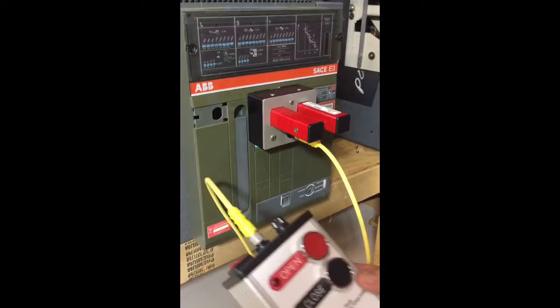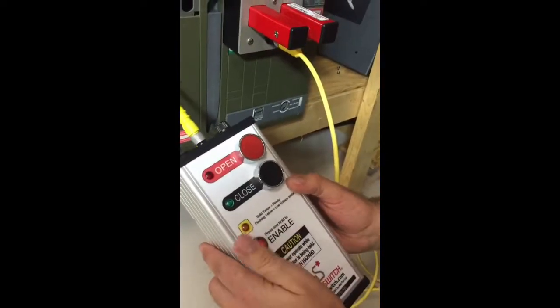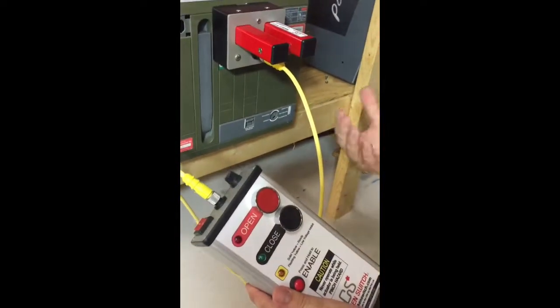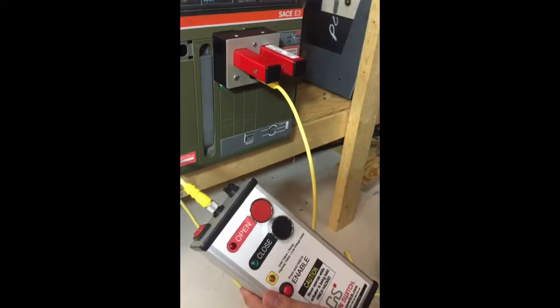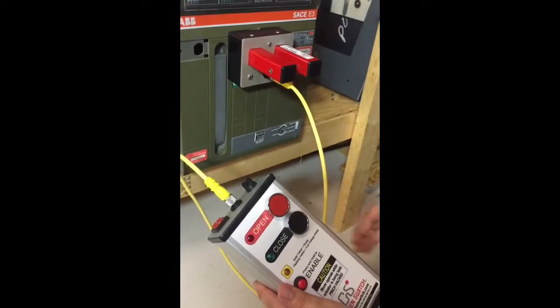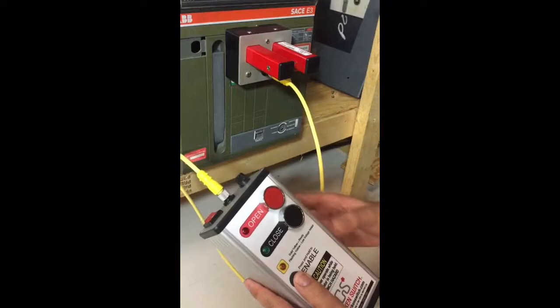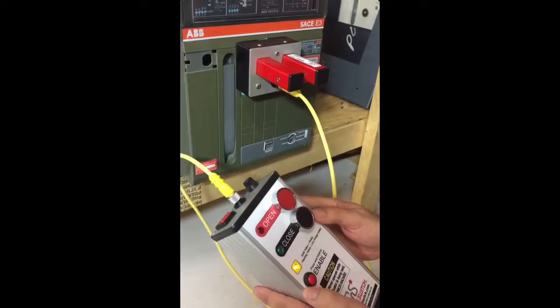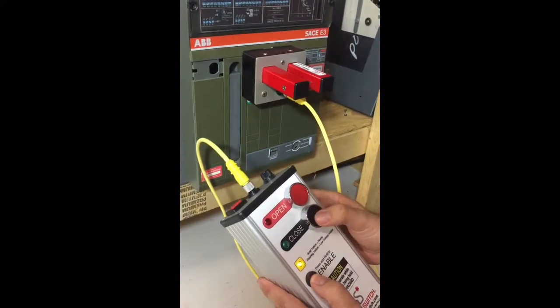I'll grab the remote and I will be positioned ideally 30 or 50 feet away depending on how far I need to be due to my arc flash requirements. And I'll hold the enable button and close the breaker.